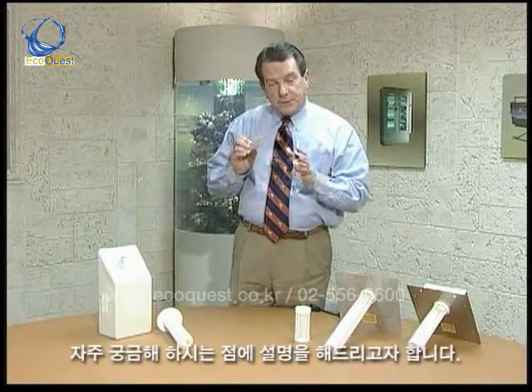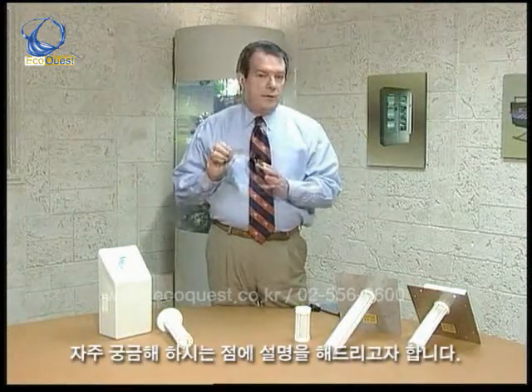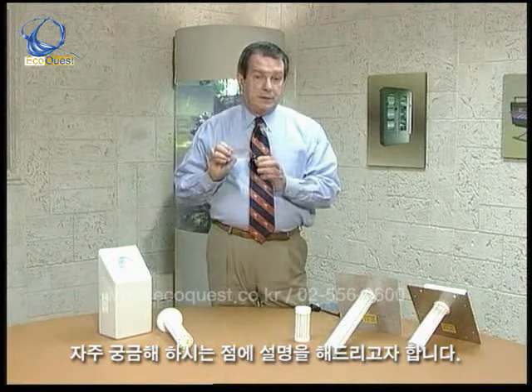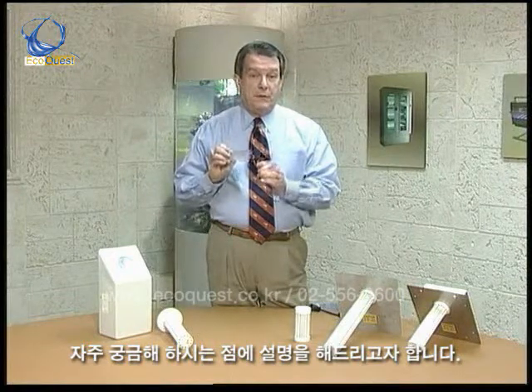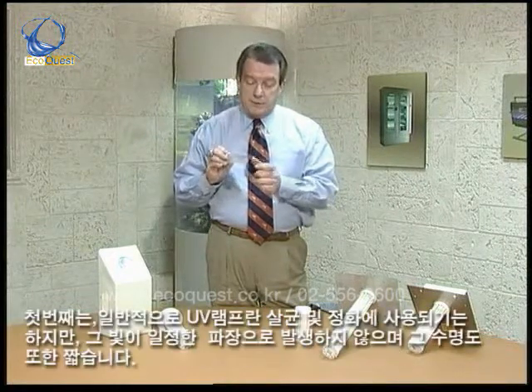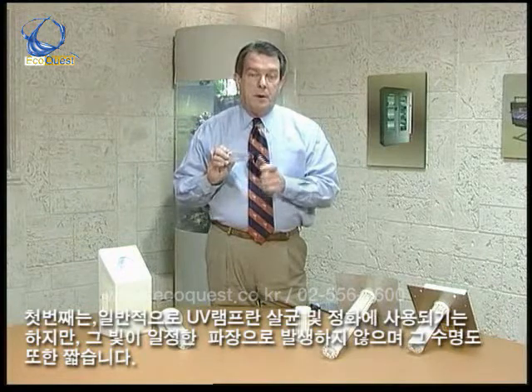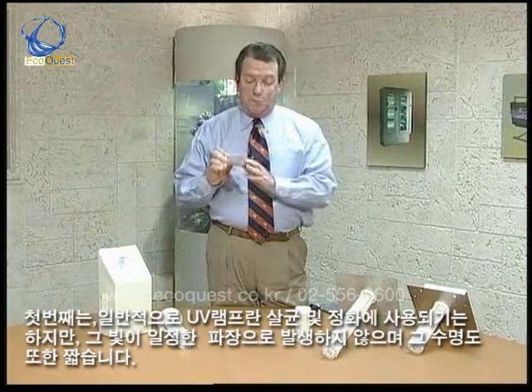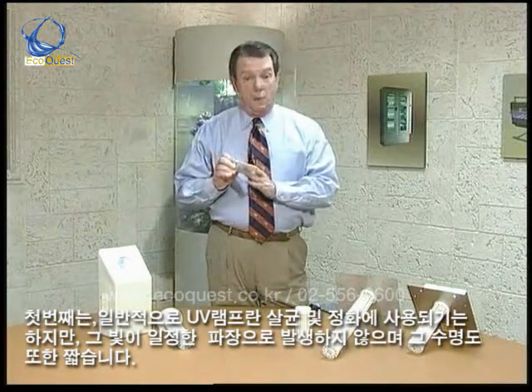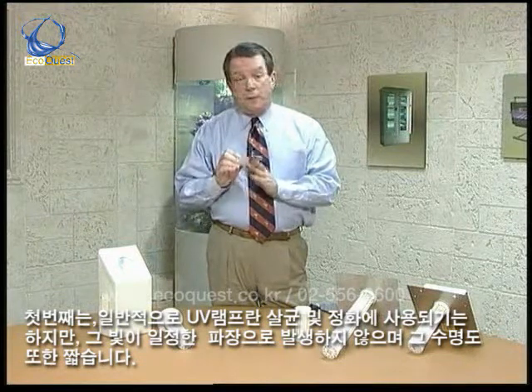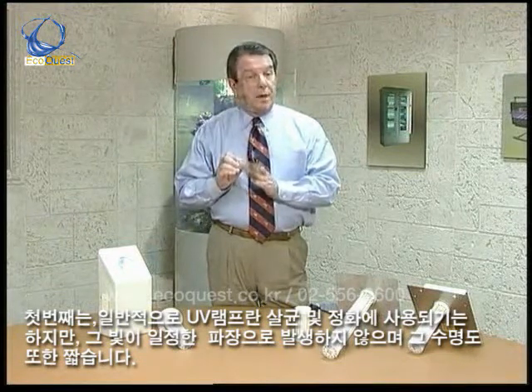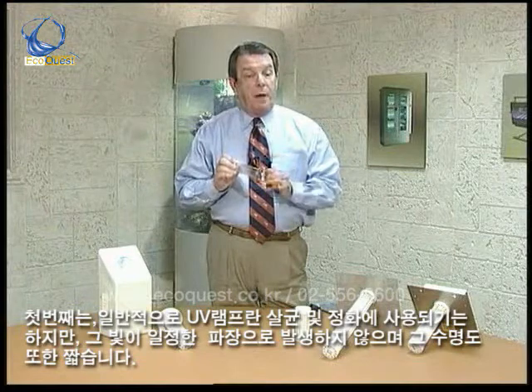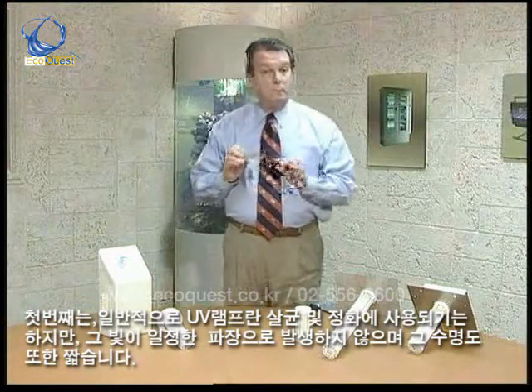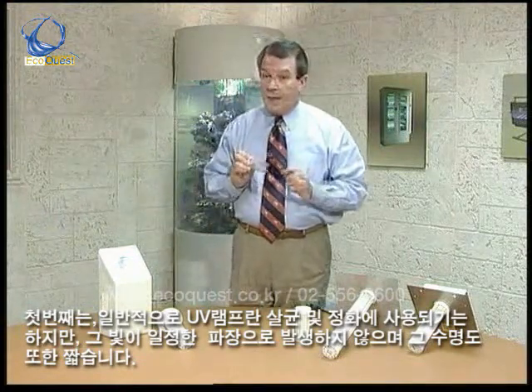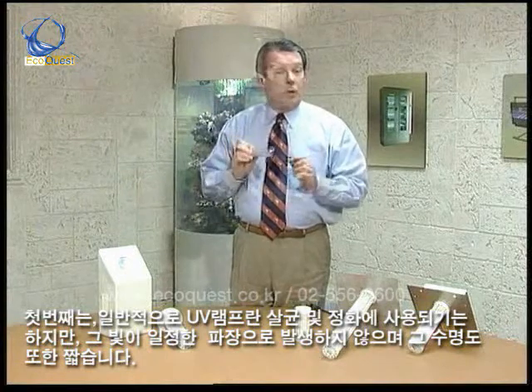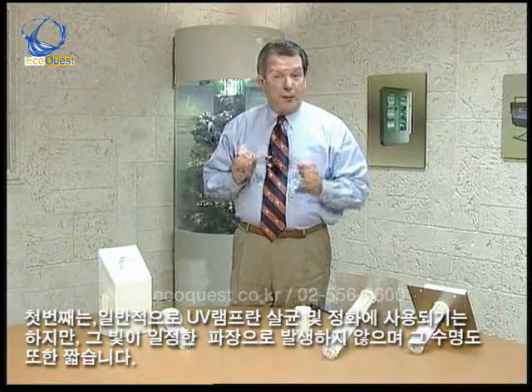Interesting is that that light energy reduces or diminishes at an incredibly fast pace. In most UV applications, within 3 inches of the bulb, 90% of the original energy found at the surface has already gone. So the important part about UV is it needs to shine on something for an extended period of time. Because even though the light is much weaker than it was when it was first created, it has all the time in the world to shine on a coil that has mold.